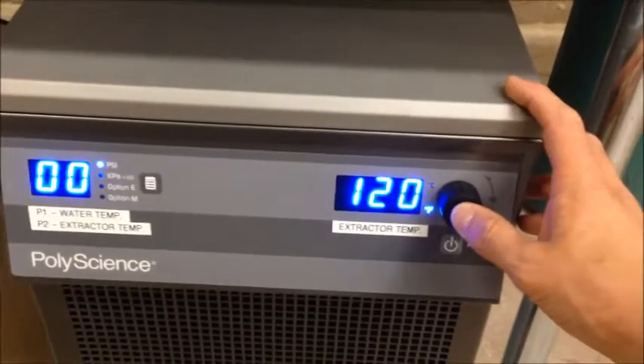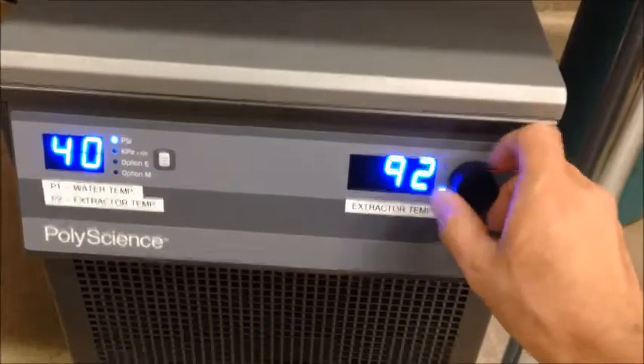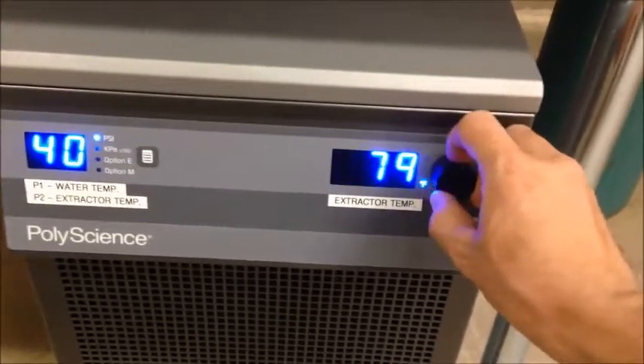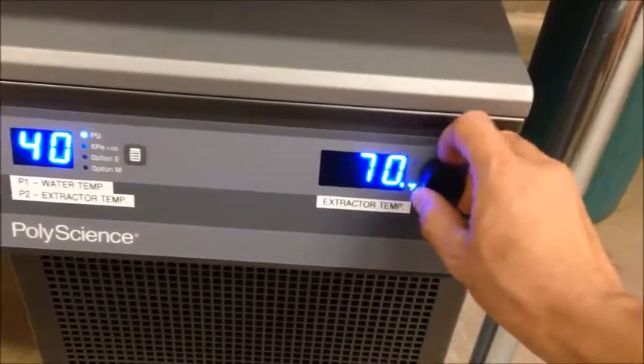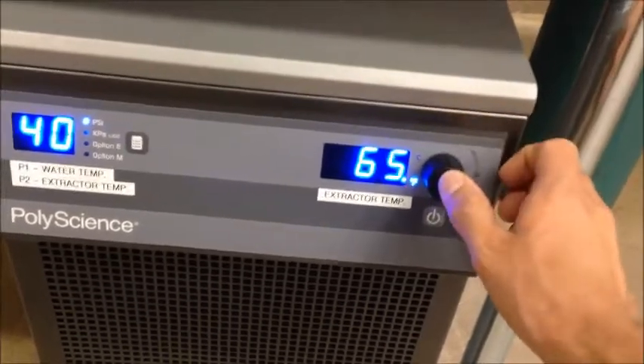Ensure that your 1 liter system is plugged in and that your pump is plugged in. First thing you'll do, come over here, turn your chiller on, set your set point. So we're going to turn this down to 65. Recommended setting. All this can be found on page 17 of the owner's manual. So we've got our chiller set, 65.